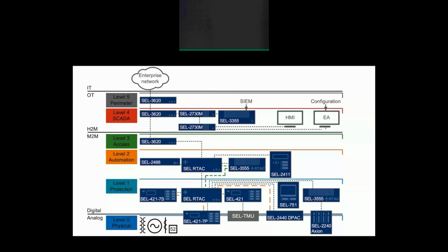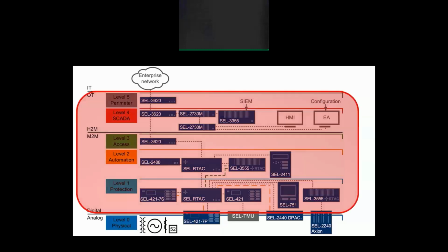For example, consider the typical ISA and Purdue model of a control system where the physical level is the process at the bottom. This level 0, in this case, is the process of generating and delivering electric power. In other examples, it might be a surgical theater or aircraft control system. Above that, we have the safety and protection system. Above that, automation. Above that, access to other substations and control centers. Above that, the supervisory control and data acquisition. And then the electronic perimeter where communications change from OT, operational technology communications with machines, to IT on its way to level 6, which is the people.